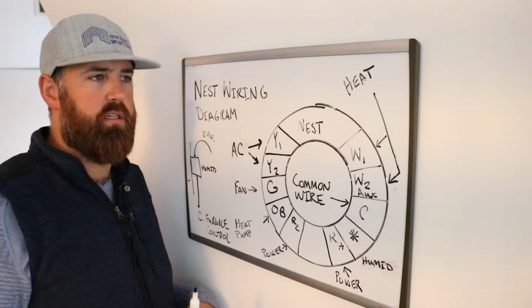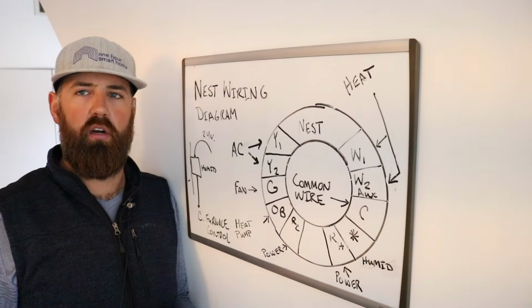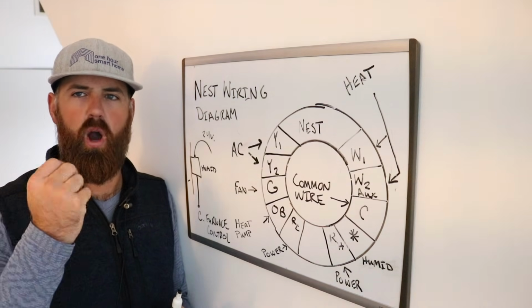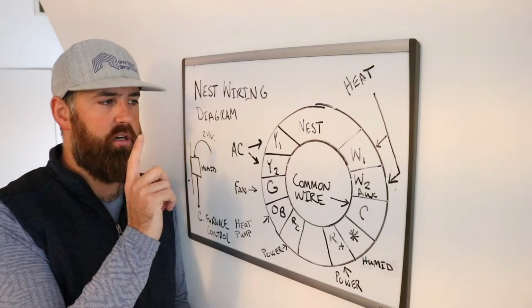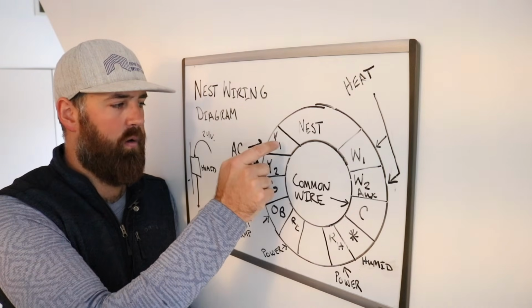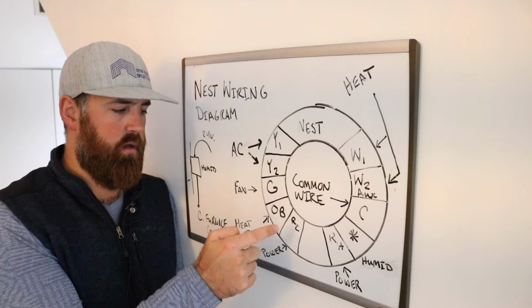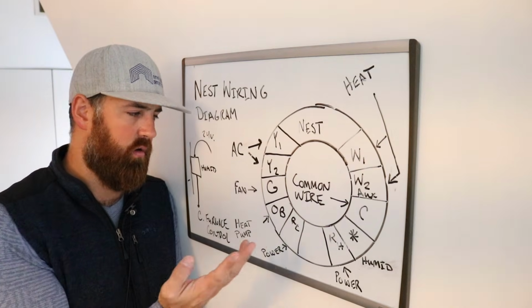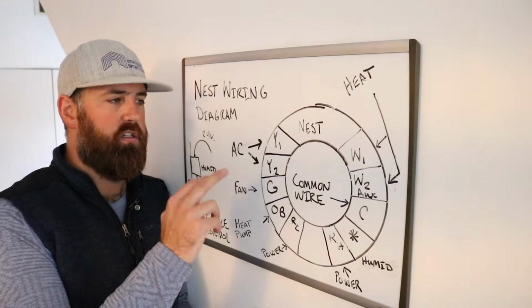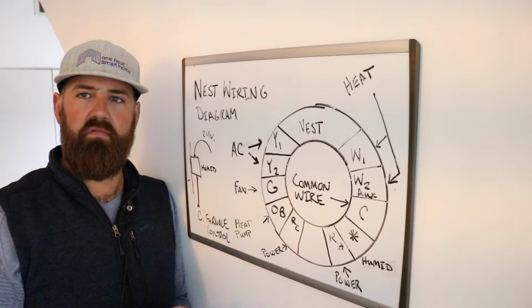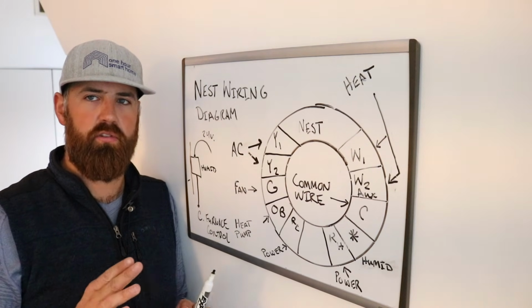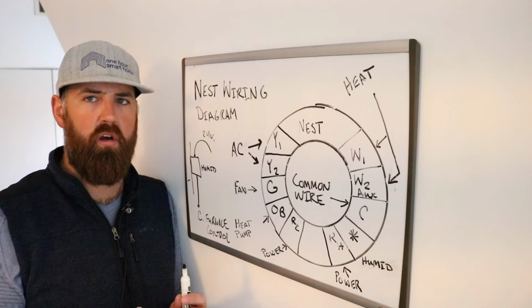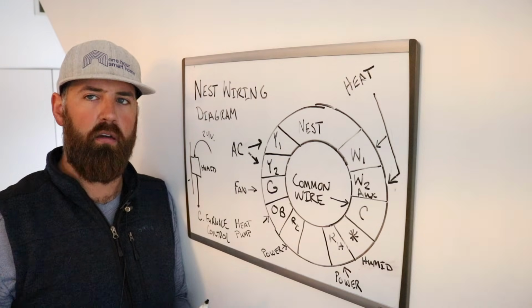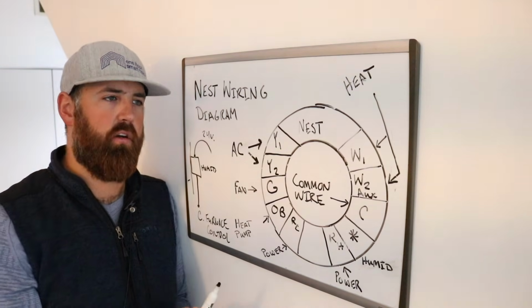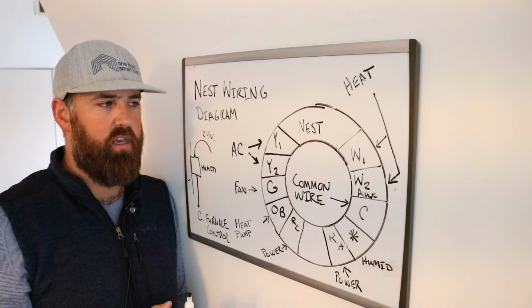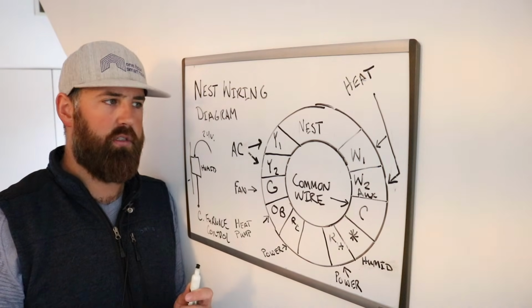W1, for most people, if you have just a regular heating and cooling system, you've only got about 4 wires to your thermostat—you'll just have W1, Y1, G, and power connected, RC or RH, it doesn't really matter. W1 is just regular heating for most people. There's no single stage or second stage, it's just one continuous heating cycle and level of heating—your burner's on and the fan blows.